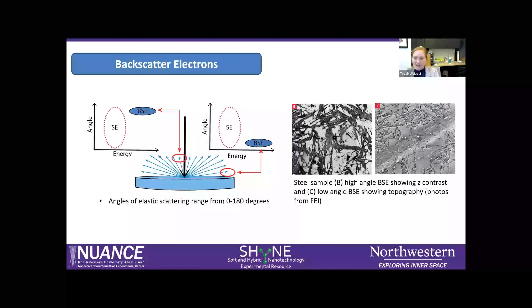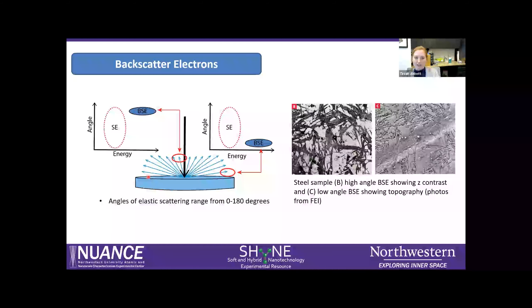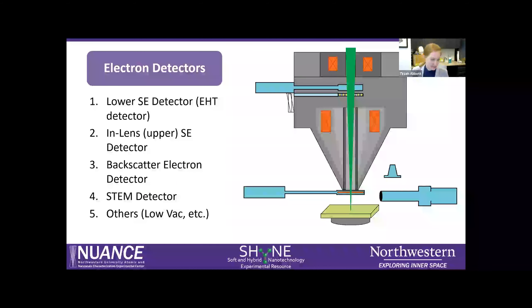Backscattered electrons can exit with different energies, but the angle at which they exit tells you different things. High-angle backscatter signal along the optic axis gives nice compositional contrast, whereas lower-angle backscatter signal can give topographic information. Some backscattered electron detectors can be set up to filter different types of backscatter signal. With that, I'm going to pass it over to Nick to talk about the different types of electron detectors we have at Nuance.